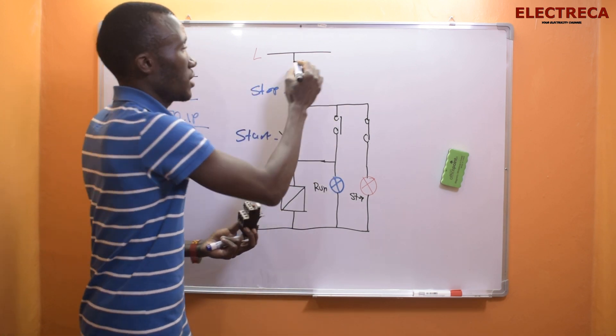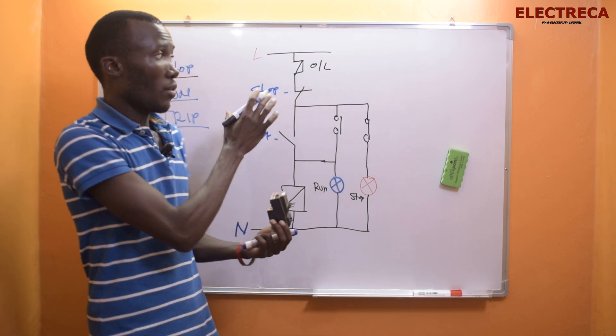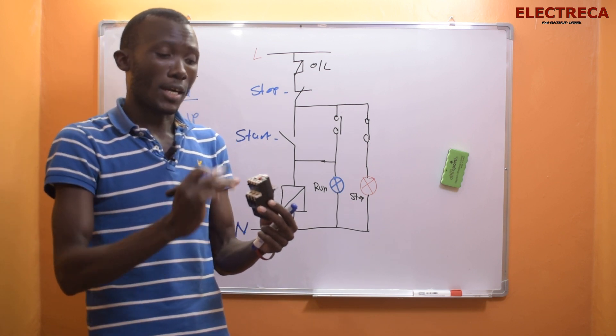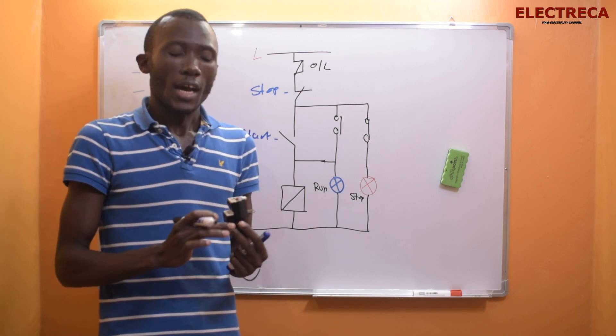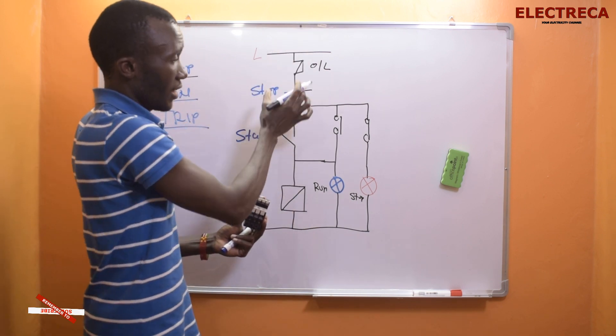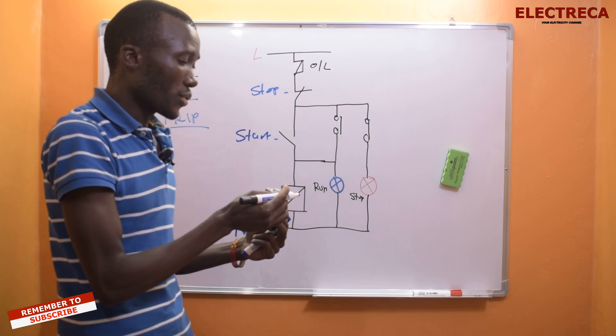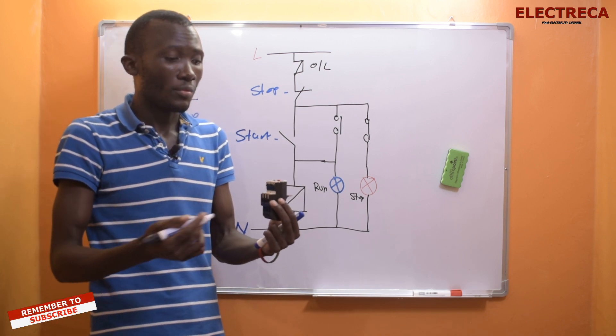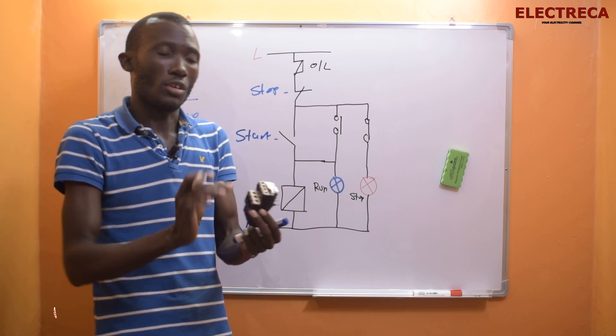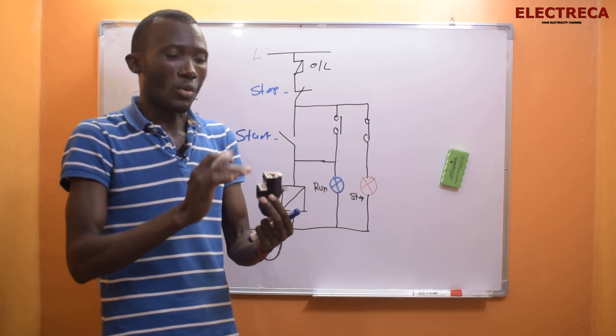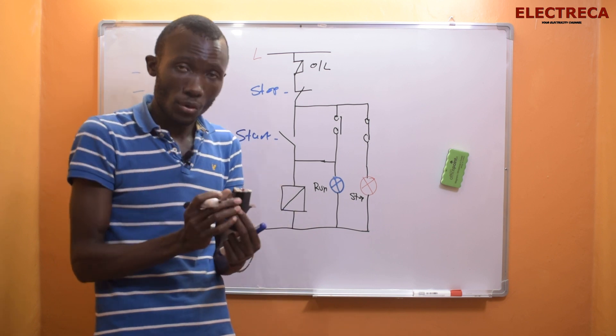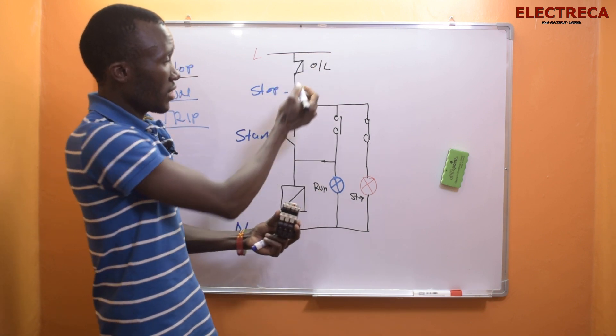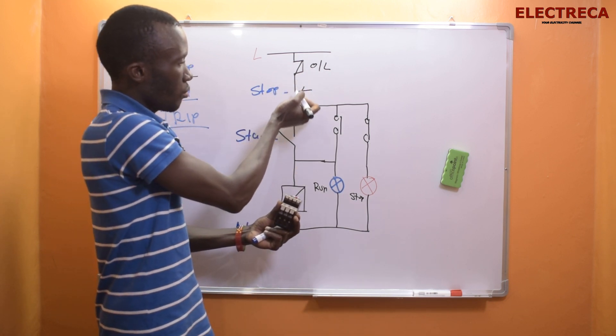This is an overload. Now how do we connect an overload? This overload has got two sets of contacts - it has normally closed and normally open contact. When we are connecting in our circuit, we use normally closed. This normally closed operates the circuit and de-energizes the circuit in the event of any fault. In case a fault occurs, the normally closed becomes open and then the open one becomes closed.